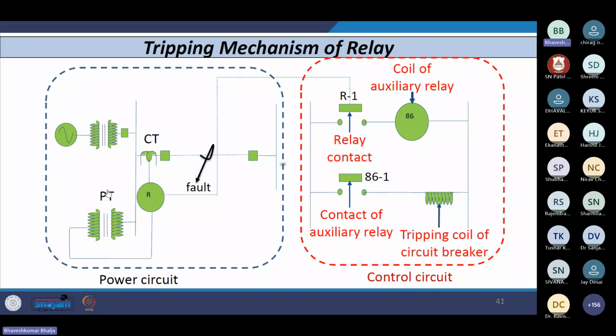No need to go for any interruption. No need to go for any maintenance. You don't need to send any lineman to find out the type of fault or the location of the fault. This is absolutely not required, right? This is what utilities are using nowadays at all 220 kV and above in our country. I don't know about 132 or 66 kV. Definitely at 66 and 11 kV they are not using it. Maybe at 132 kV they have installed it as a pilot project at some place, but I am not aware of this.